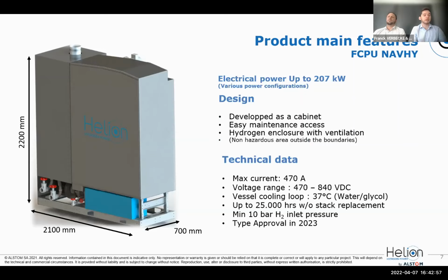Our design is based on a cabinet, meaning all the components are accessible from one side, which facilitates maintenance for the customer. We also include a hydrogen enclosure with a dedicated ventilation system and continuous hydrogen detection, meaning the room does not have any hazardous area outside the boundaries.